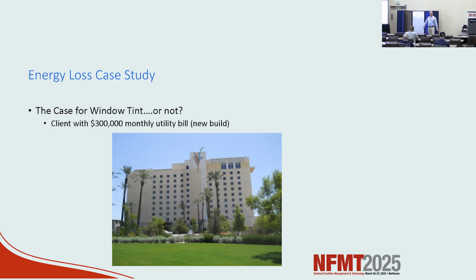They window tinted 2 of the rooms, only to find out—I'm going to break it to you guys—window tint is one of the biggest problems you can ever do. It goes on the inside of the room, not the glass itself. And what happens if we're slowing down heat transfer? It hits one pane of glass, then hits an interstitial sealed space with argon or krypton, then hits another glazing unit, but then it has tint. What does tint do? It reflects.